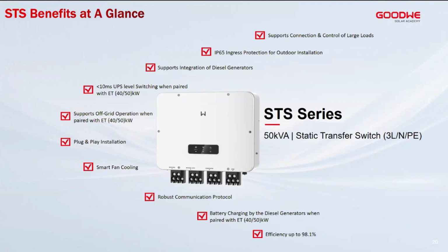The STS is very robust in communication. Communicating to the inverter, it's able to handle up to a 100-meter distance in between. So you can install the ET series inverter, let me say, next to the PV panels and install the STS in the power room. In that way, you're reducing the cost of your installation because you have fewer cable runs to the inverter itself: only one AC cable run and one communication cable to the inverter. And in the power room, you can loop in the cables to the critical loads, a cable to the generator, and a cable to the incoming grid. That's how robust it is.